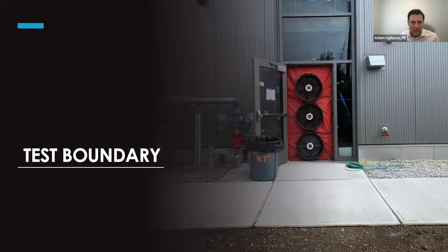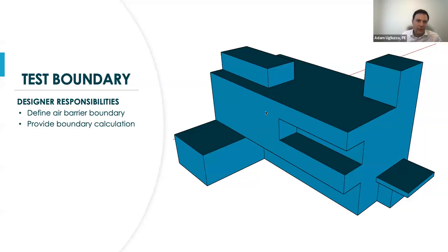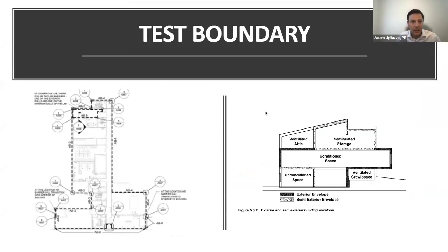The test boundary, another key part. This starts with the design, but it can also happen later on. You can figure out the boundary criteria that better fits the design of the building before you do the test. It's very important to establish this before you get out there and do the test. So what's that six-sided box? How complicated is it? We need to make sure we're drawing a line around this thing to really understand what's in and what's out, and that surface area is included in the calculation.